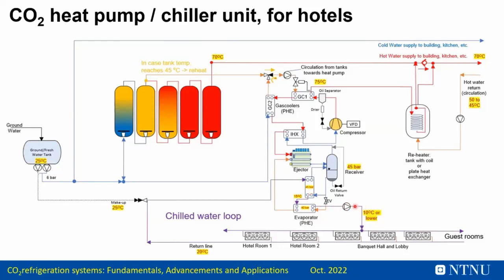So in this case we can provide very efficient cooling and at the same time utilize the heat to produce the hot water, and that's exactly what you need in a hotel. So a CO2 heat pump chiller for a hotel is a win-win for both the end user and the environment, and it will be a success after all the supermarkets in the next years to come.